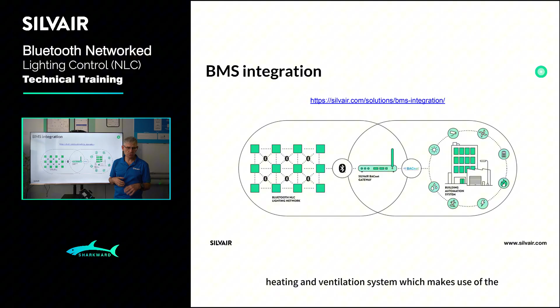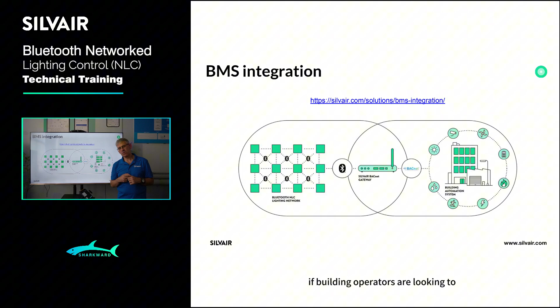So for example, for bigger buildings through BACnet, we can do similar integration with HVAC as for smaller buildings, the thermostat connecting over Bluetooth NLC to lighting sensors. So through BACnet gateway, the occupancy information from lighting sensors can be forwarded to the BACnet-based heating and ventilation system, which makes use of the zone occupancy, and in particular implements the so-called occupied standby concept. This is precisely defined in the ASHRAE 90.1 standard, and is becoming a really important feature if building operators are looking to enhance or improve their energy savings.